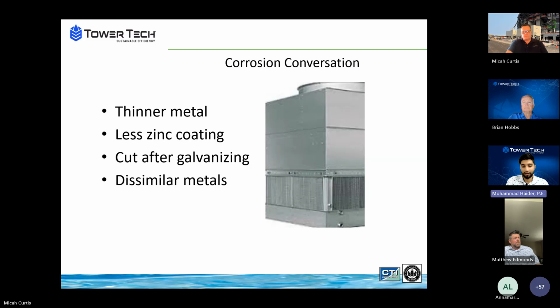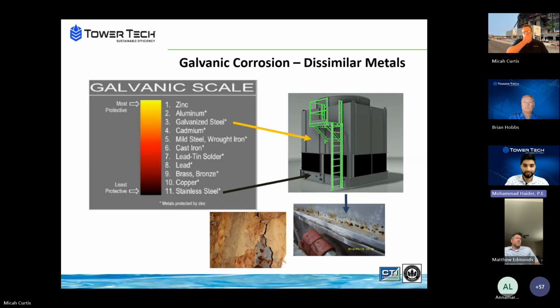So if you have just galvanized steel or just stainless steel, you would have much longer performance as opposed to mixing those two together. A lot of the times when people have a cooling tower, they say, okay, well, the basin itself is going to be the most exposed to water, so let me make the basin stainless and the tower itself will just be galvanized. What you've done is you've actually created an anode and a cathode, which, on the galvanic scale, creates a small battery, which essentially accelerates corrosion between the two metals. So dissimilar metals are a big no-no.